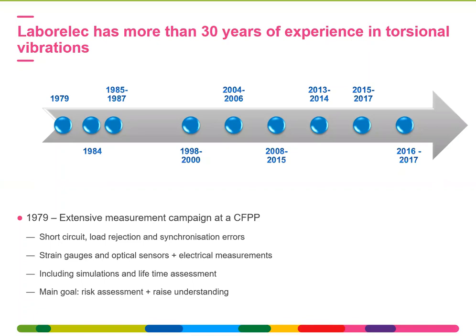So the risk assessment was done by deliberately exciting the shaft line by means of short circuit, load rejection, synchronization errors, so all typical transient events, and then measuring mechanically by means of strain gauges and optical sensors at that time, as well as electrically at the generator, the voltage and current values. Simulations were also performed, so the model of the shaft line as well as of the grid, in order to be able to assess the lifetime.